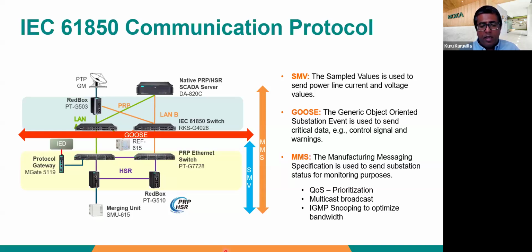The command is typically in the form of what you call a GOOSE message. And this message is what is communicated across from one relay to other relays in terms of the different control actions they want to take, as well as, depending on the system, going back all the way to the individual devices to execute that action. And then lastly, you have what you call the MMS, which are the status messages. So this is essentially letting all the relevant equipment, all the way up to the SCADA system, know the status of various different devices in the system.